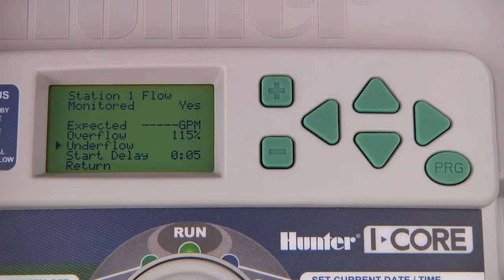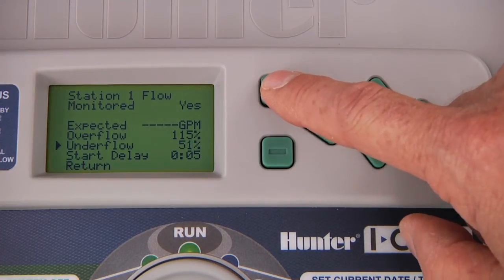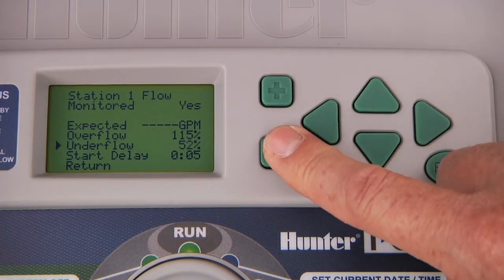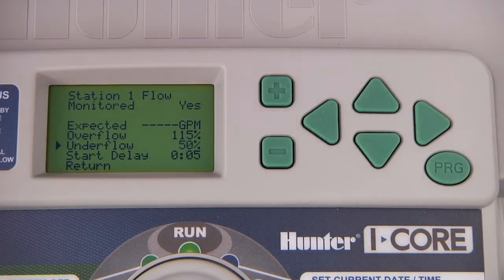Likewise, the underflow is the limit at which the controller reacts when underflow conditions are detected. The default is 50%, which means that if the controller records flow conditions 50% under the expected flow, it will send an underflow alarm and shut down the irrigation for that station. You can change this number from 10% to 100%.